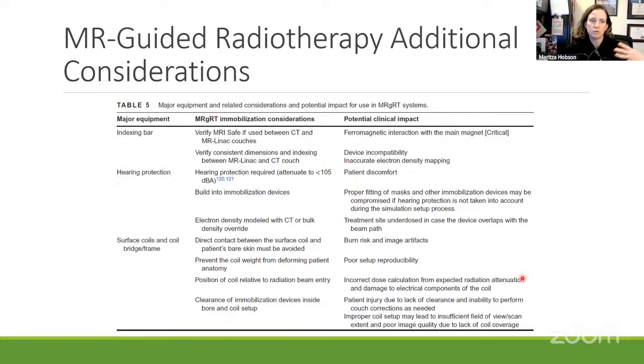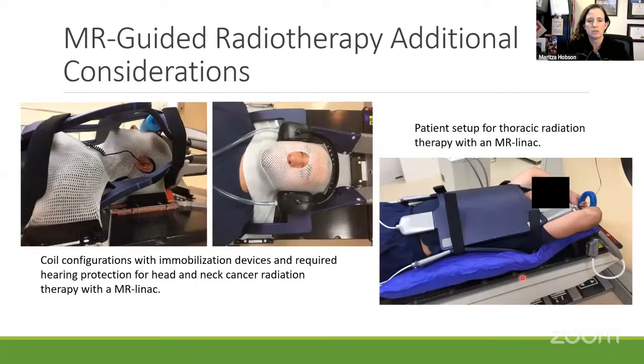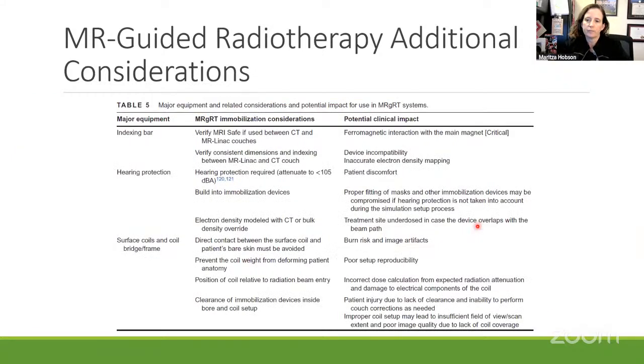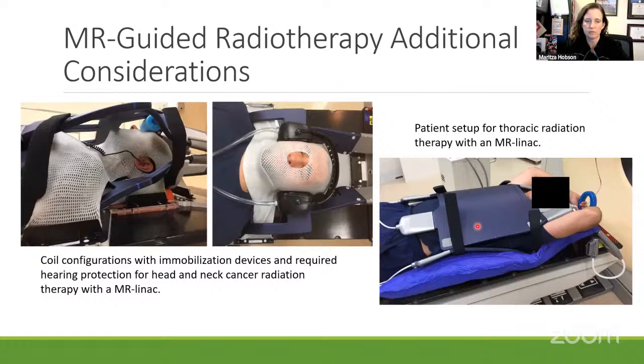Okay, so when you place the surface coil on the patient, here's some great examples. This is from the MR Linac system that I've used. The positioning of this coil is important, because you don't want any attenuation through things that weren't in there from your MR simulation. It's pretty similar to a CT sim scan, where you want what's in the scan to be exactly where it is. Okay? Because it could lead to differences in attenuation along the beam path versus the setup. Not really different from CT sim, but because of your limited field of view, you may not be thinking about that. Okay?